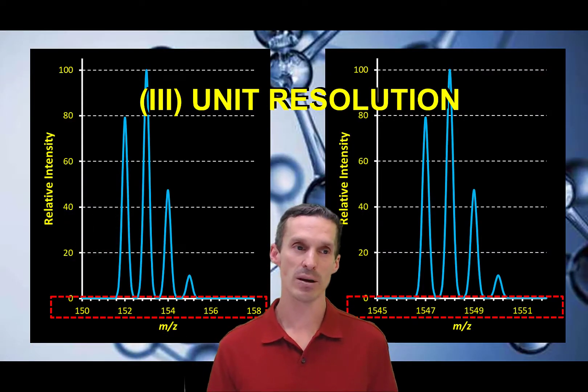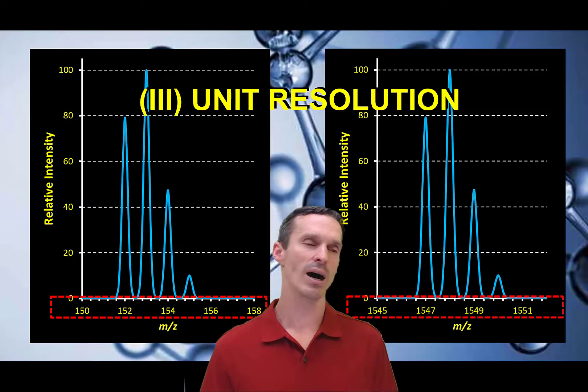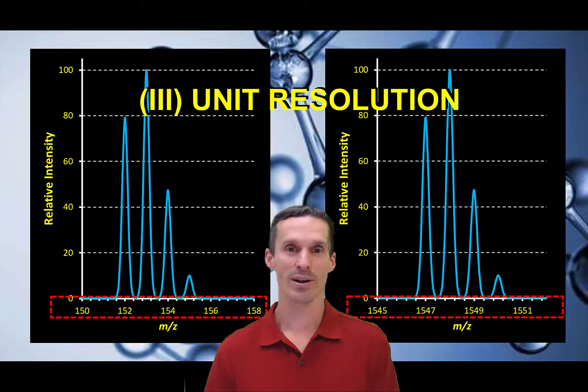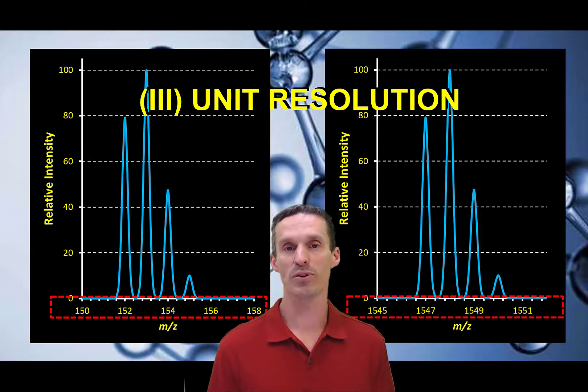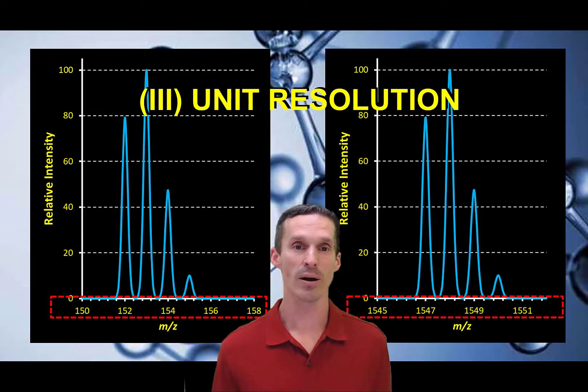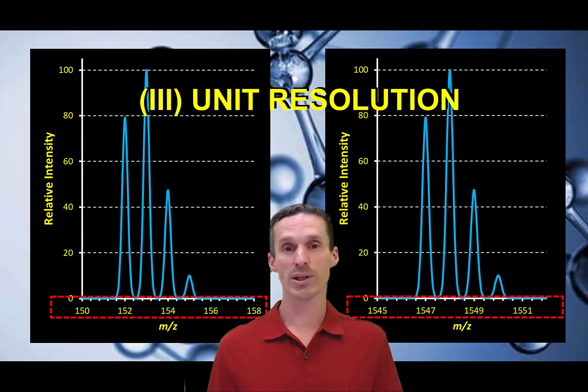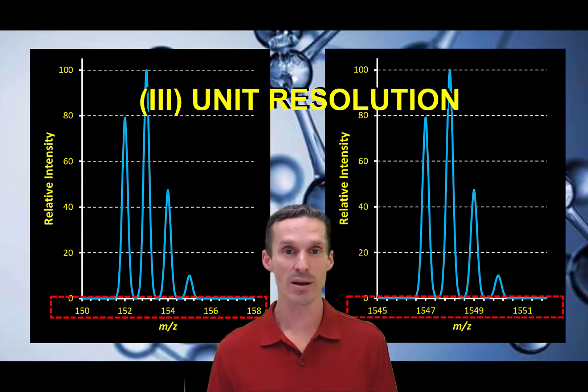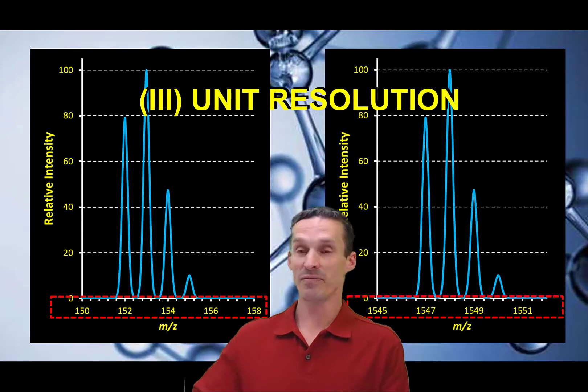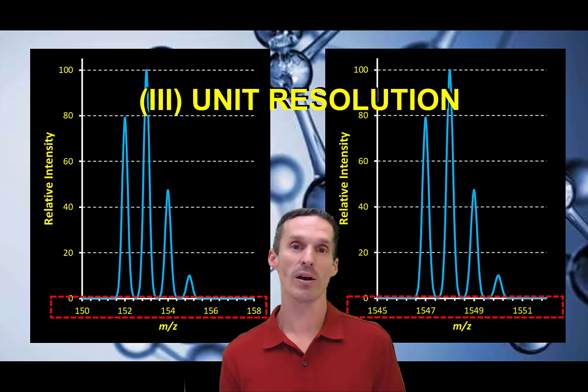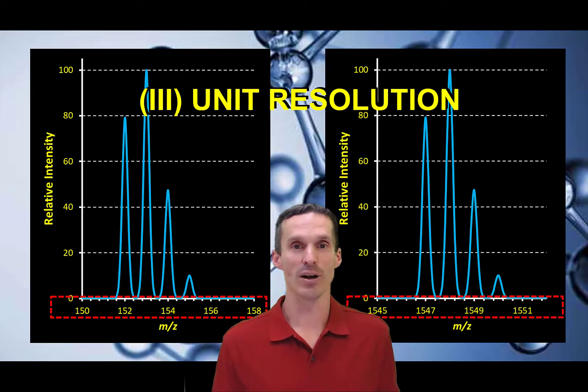There's one other definition I want to present: unit mass resolution, which is relevant to ion traps and quadrupole instruments — at least it used to be back when they weren't very high resolution. Unit mass resolution simply means you have two peaks that are one mass unit apart and they appear to be resolved, with about 10% overlap. It doesn't matter if the peaks are at 152 and 153, or at 1547 and 1548 — they're still one mass unit apart and resolved. In that case, you just report that they have unit resolution.